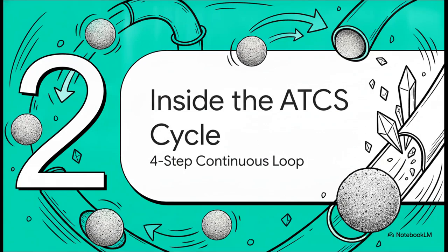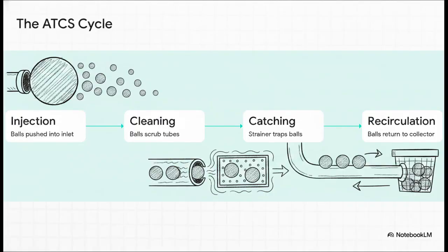Inside the ATCS cycle, so how exactly do we fight back without slowing down operations? The system actually uses the chiller's own natural water pressure to run this continuous, high-speed, four-step loop. Step 1 is injection. It literally pushes these sponge balls, which are just a tiny bit bigger than the tube's diameter, right into the cooling water inlet. Step 2 is cleaning. The immense water pressure forces those balls through thousands of condenser tubes, gently scrubbing the walls clean before that scale can harden. Step 3 is catching. At the exit pipe, there's a specialized strainer that traps the balls while letting the water flow right through. And finally, step 4 is recirculation, routing those balls back to a collector so they can be fired again. And this whole cycle just repeats totally automatically, dozens of times a day.